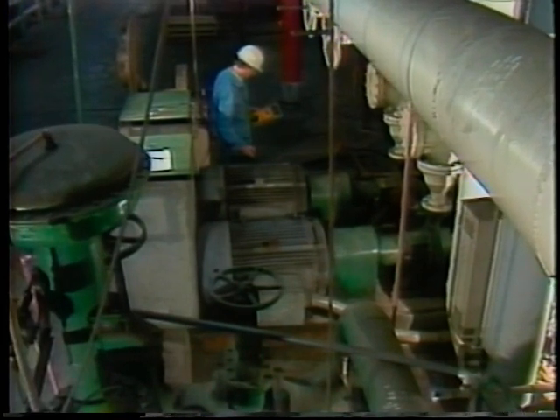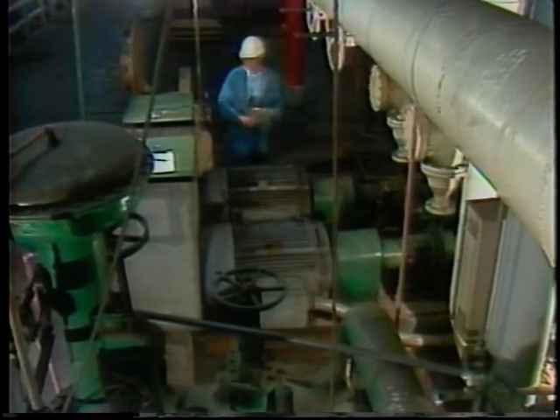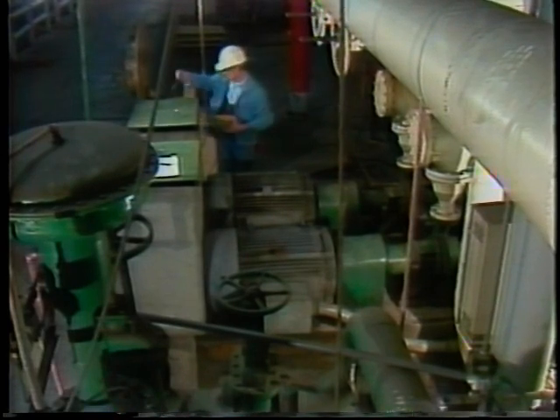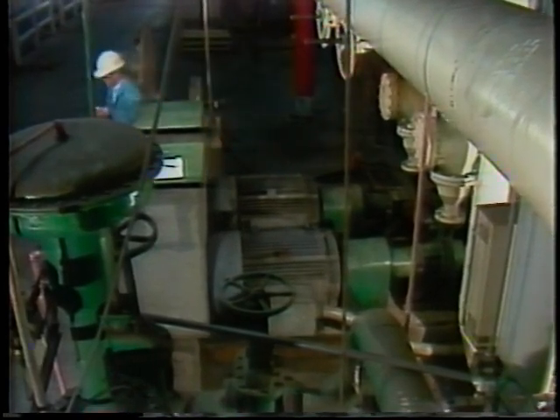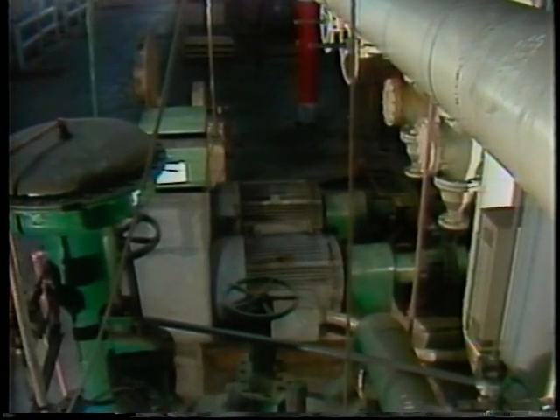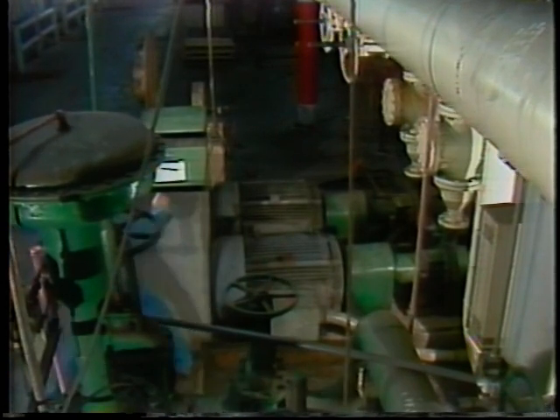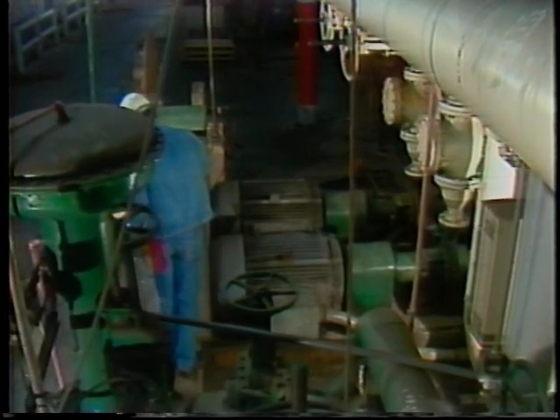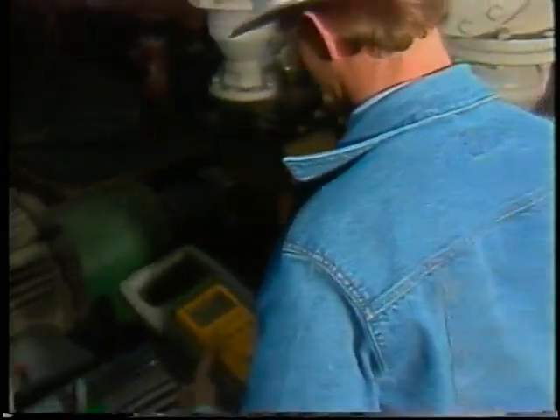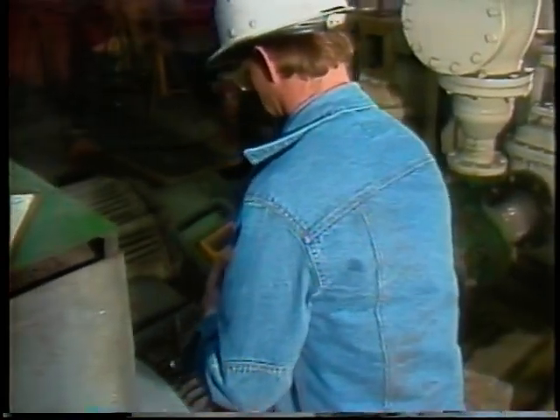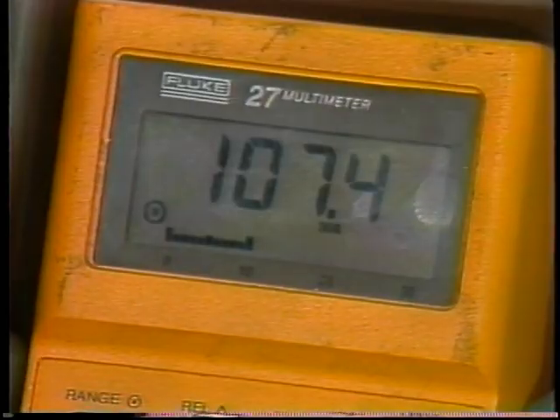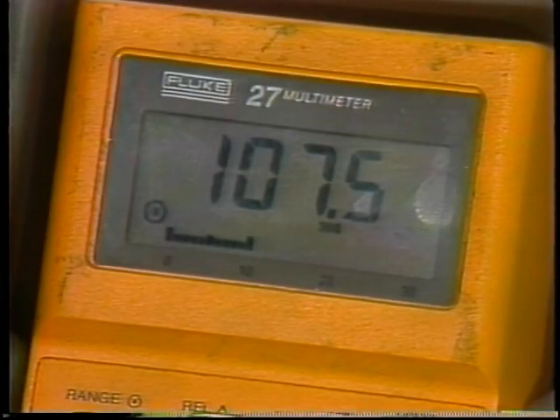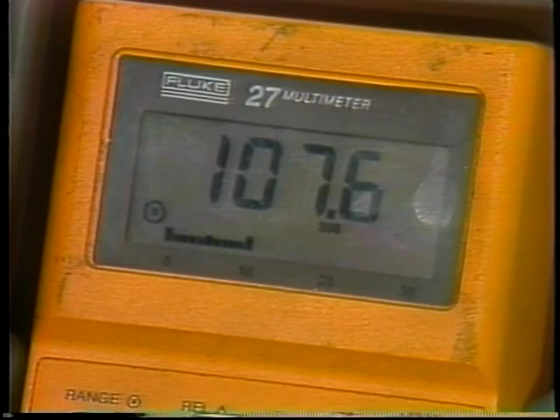Checking a motor's frame temperature is also important. Whatever kind of instrument you are using, be sure to measure the temperature after the motor has been doing its normal job for some time, and always take your readings under the same conditions so you can compare them and spot a motor that is starting to run hotter than usual. If you find a temperature reading that is significantly higher than past readings on the same motor, it means something is wrong, and you should determine what it is.